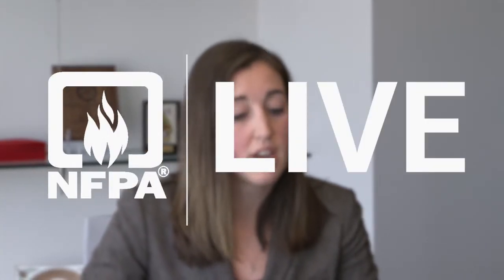Do I need a permit for every hot work job? Not necessarily. So if you're in one of those designated areas like we mentioned before, you probably don't need a permit. If you're in an area that doesn't have any combustible material within that 35-foot radius, then you don't need a permit. There is a decision tree in NFPA 51B that helps you step through different questions, and depending on if you answer yes or no, it'll help you determine if you need a permit.